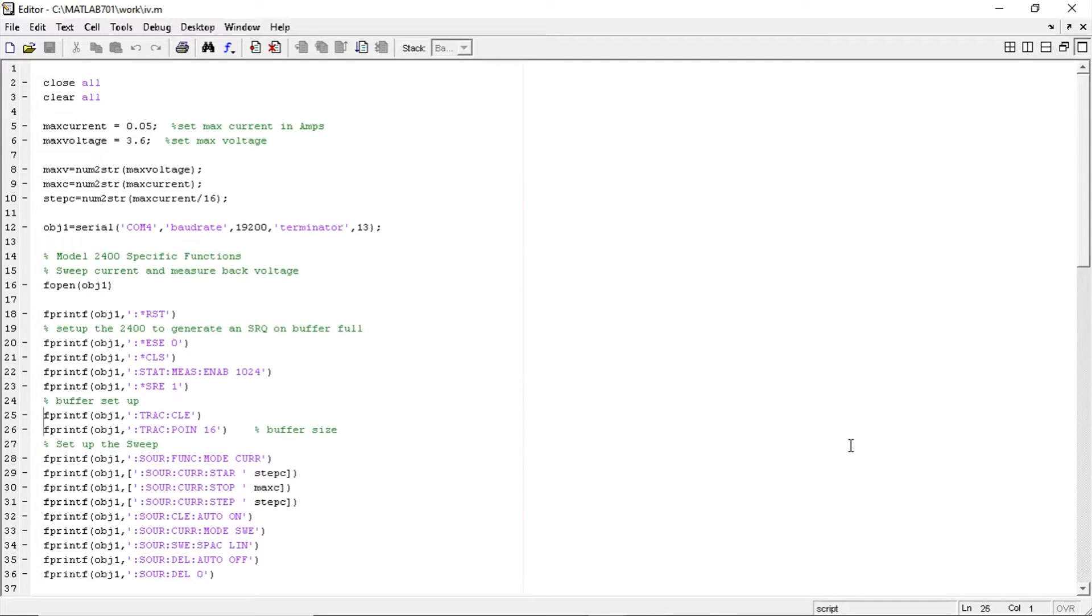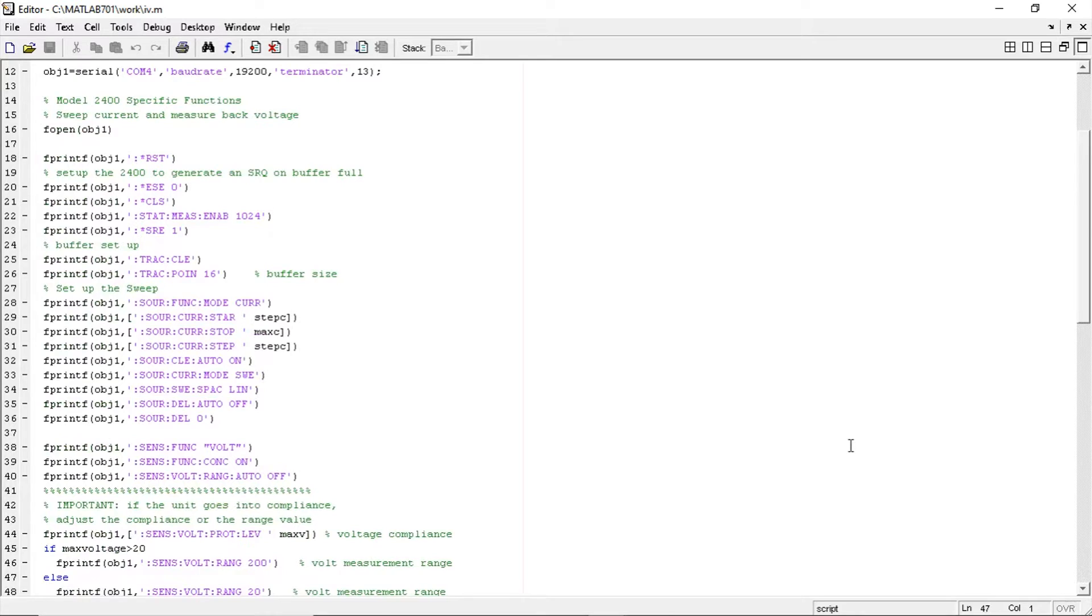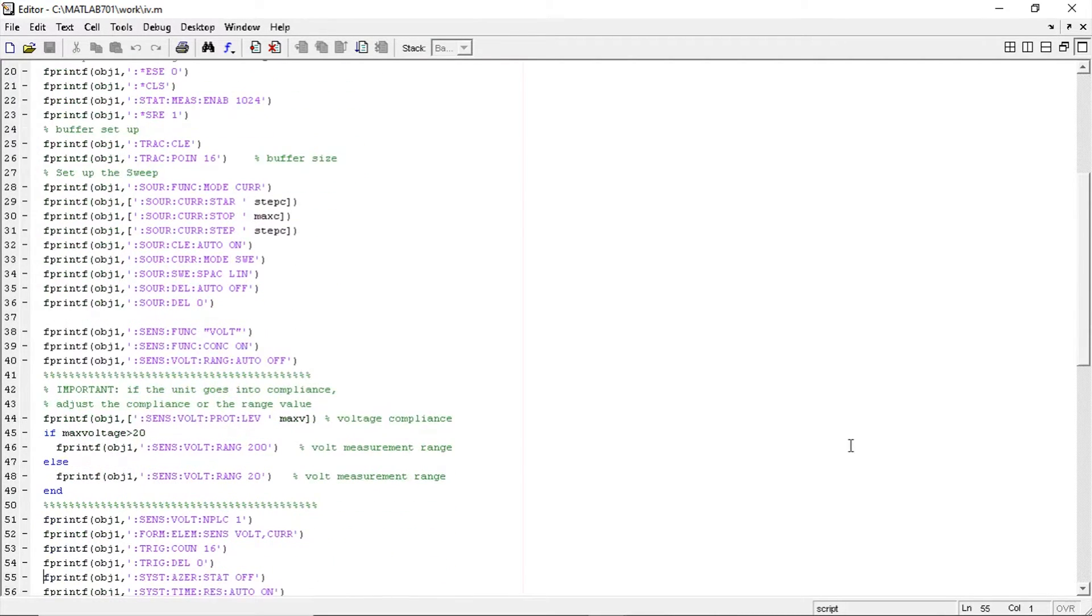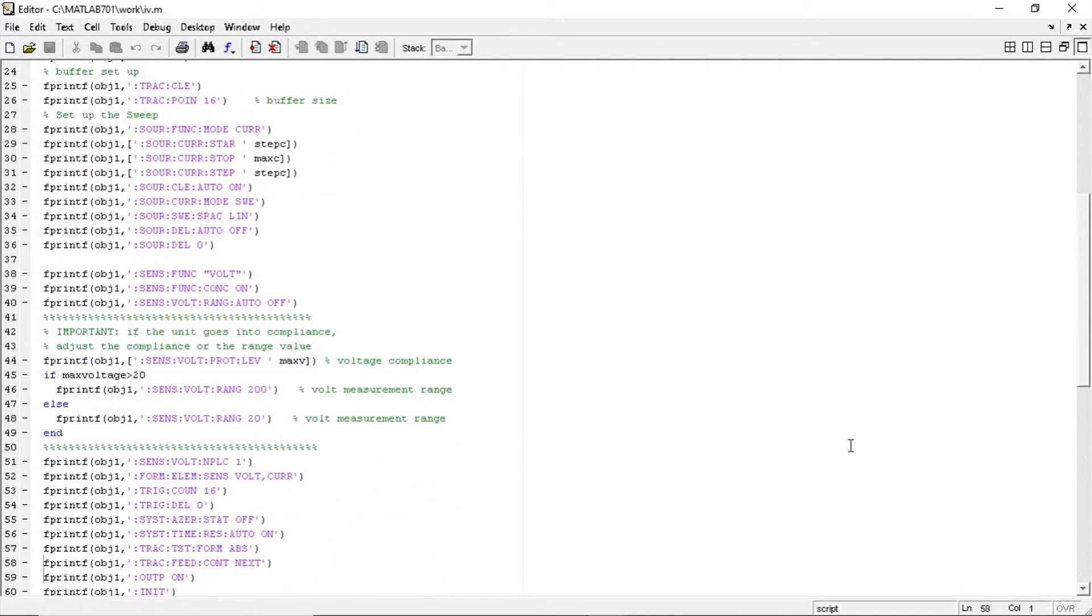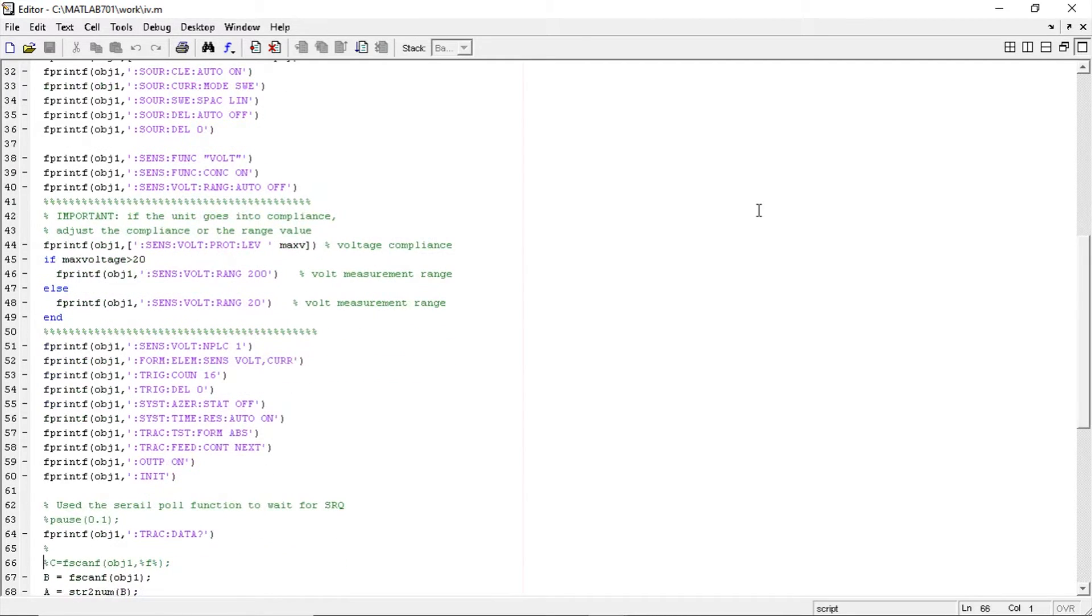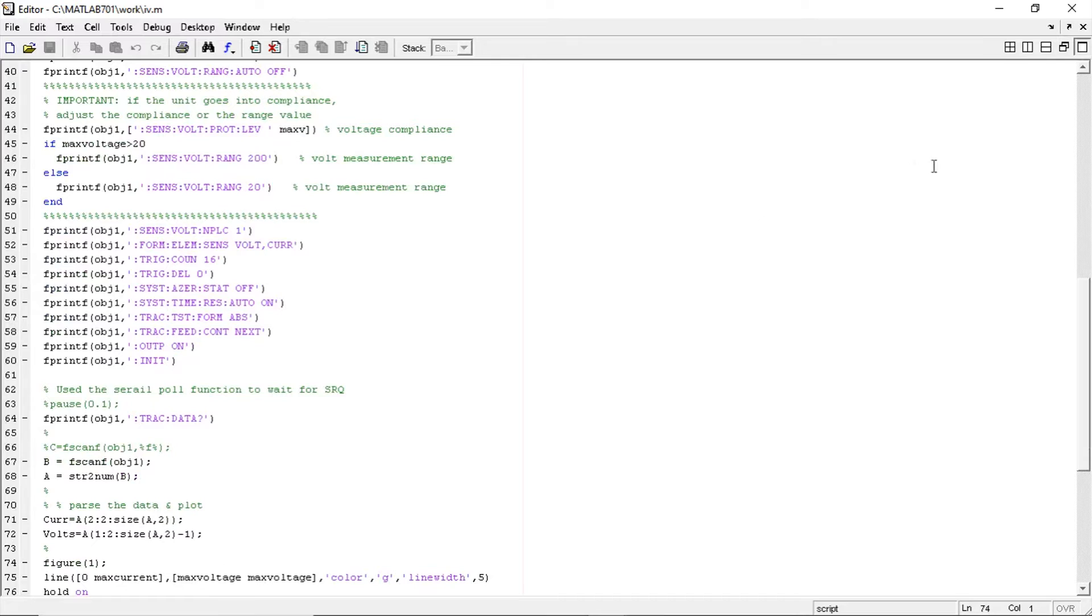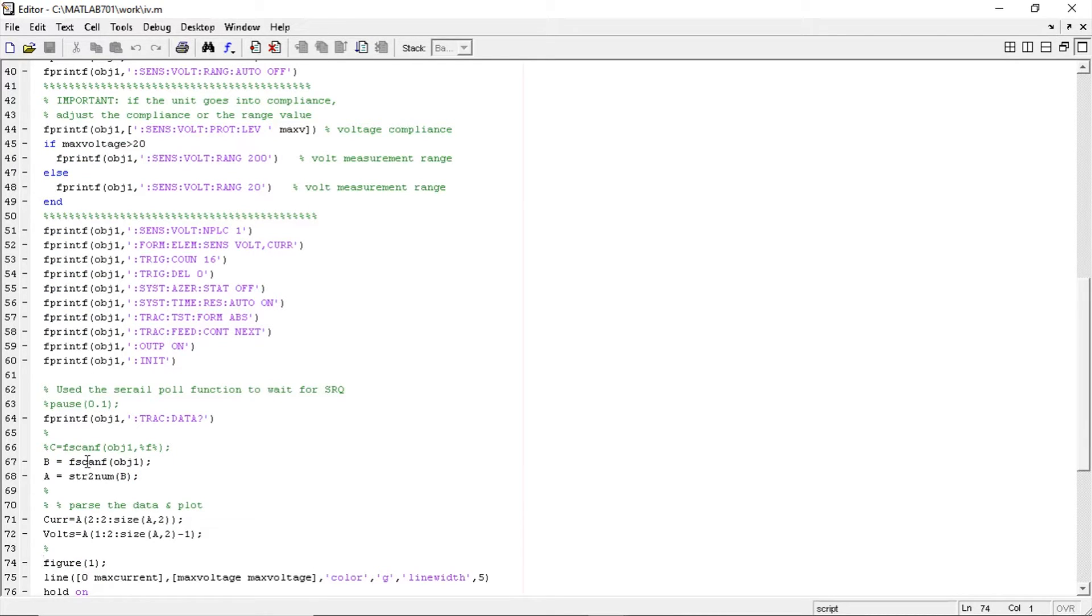So I'm setting up line 25, I'm setting up a trace, 16 point trace. And then I'm setting up the force, the source for current output. And then the sense is going to be a voltage input. And then you basically tell it to go. Line 53 is trigger, 16 counts. Automatically makes all those measurements for you. And then all you have to do is read out one string. So we're reading out the data on line 64. And it's just one long string. Then we have to parse that into current and voltage. Every other number is current. Every other number is voltage. So you need to parse that. And then plot it out.